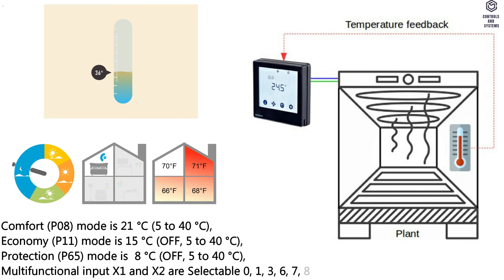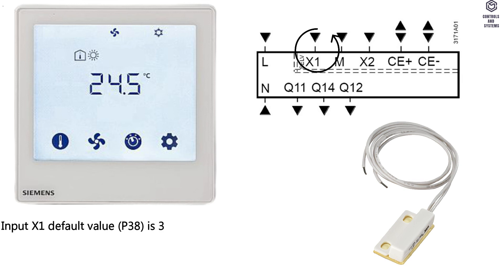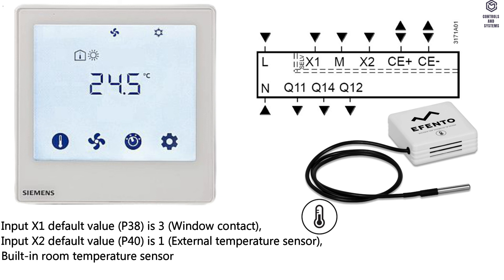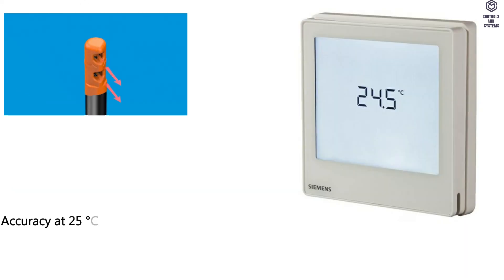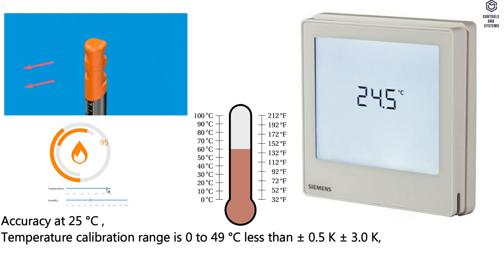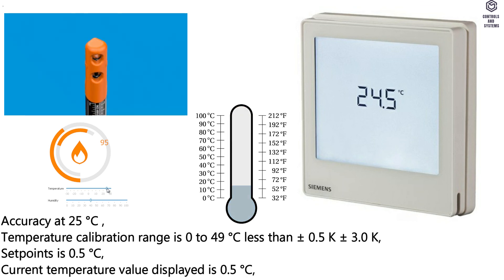Multifunctional inputs X1 and X2 are selectable. Input X1 default value P38 = 3: window contact. Input X2 default value P40 = 1: external temperature sensor. Built-in room temperature sensor measuring range: 0 to 49°C. Accuracy at 25°C: temperature calibration range 0 to 49°C, less than ±0.5K; ±3.0K. Set points resolution: 0.5°C. Current temperature value displayed resolution: 0.5°C.